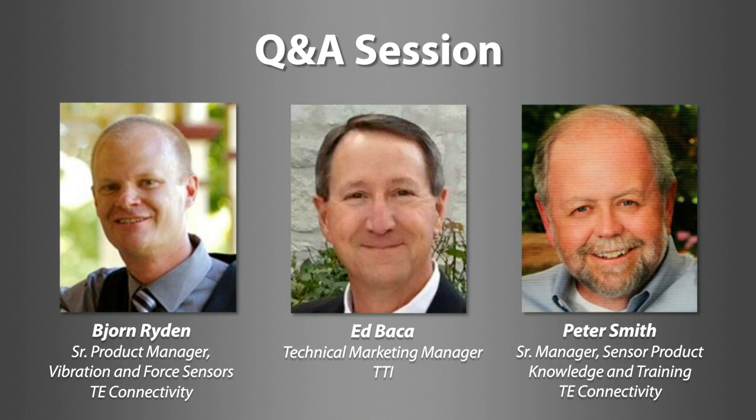Yeah, Bjorn, I'd like to add a little bit. The part of the question was, how do you decide what the difference is between a normal vibration and an abnormal vibration? Sometimes the techniques that are used include a signature analysis algorithm. What that entails is basically looking at, for example, an electric motor. You can attach the accelerometers to an electric motor, and essentially they become contact microphones, and they listen to the motor in operation. A new motor will have a very specific acoustic signature that says, yes, I'm running normally, and this is what I sound like.